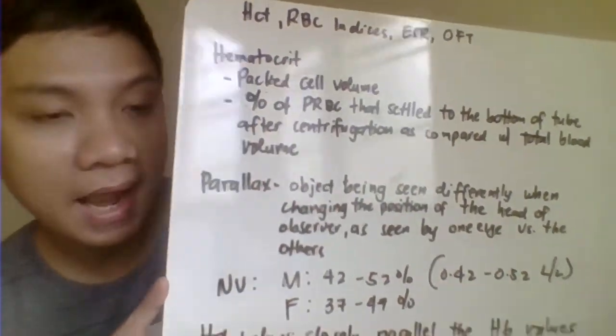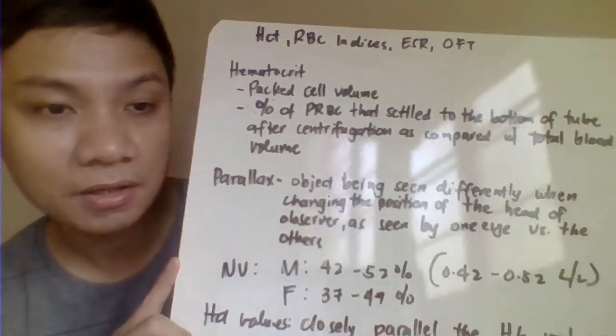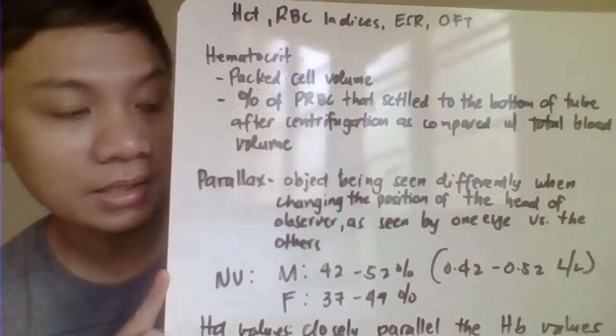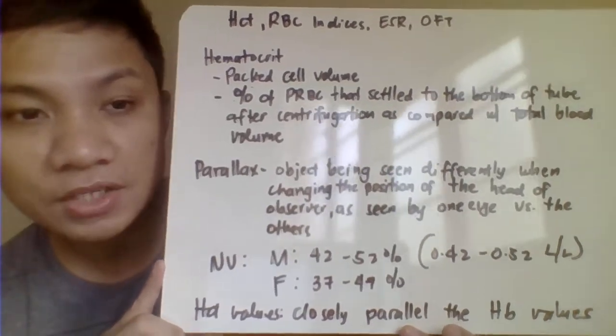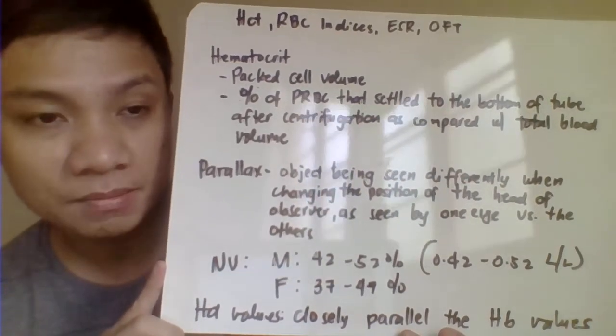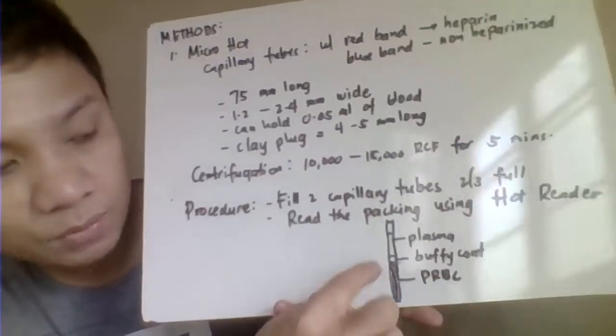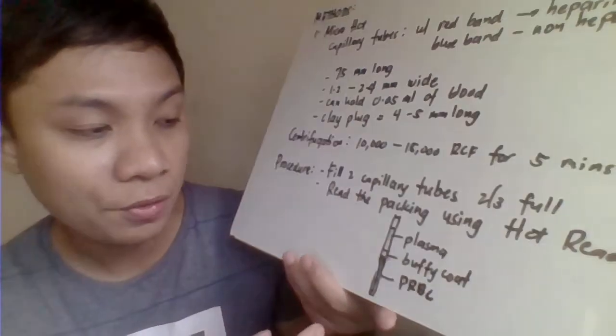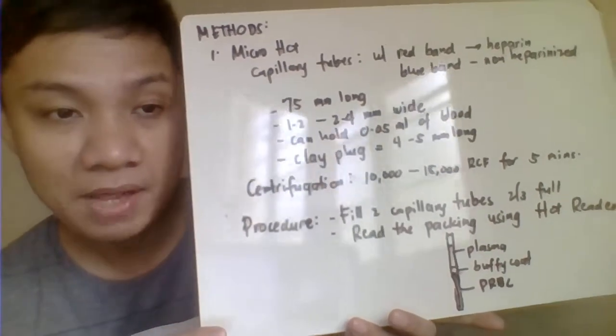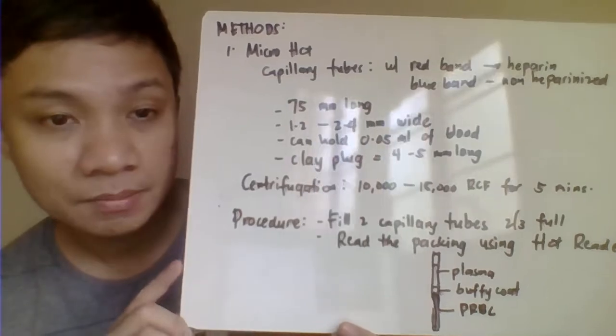The term 'parallax' is applied when reading the result of your hematocrit with a hematocrit reader. Parallax means seeing a different orientation of your object when you change the position of your head. So if you tilt your head while reading the PRBC level, you will get a different reading — that is called parallax.